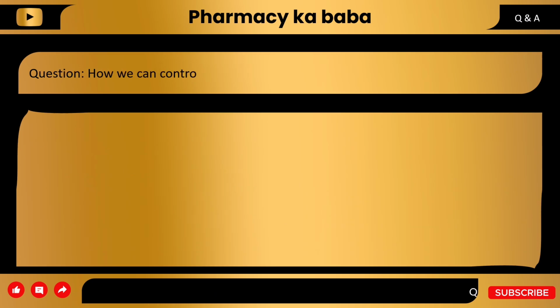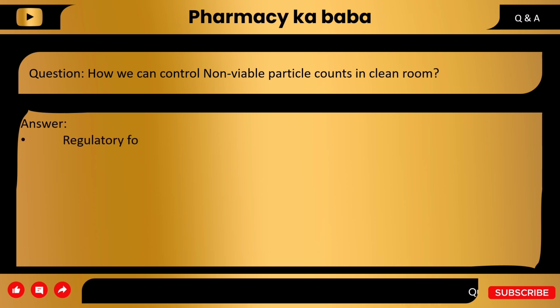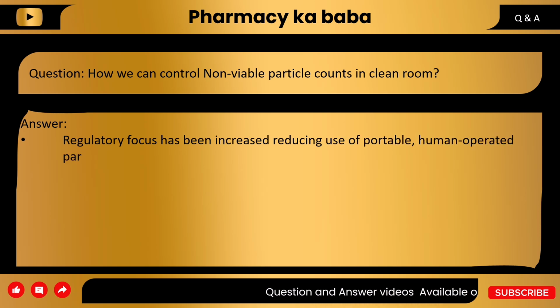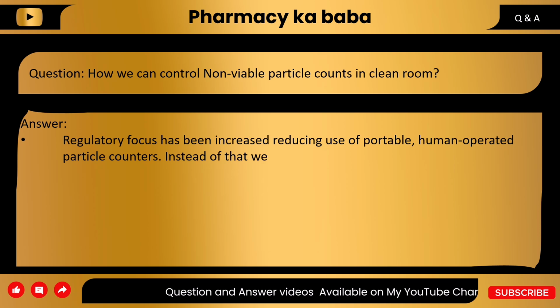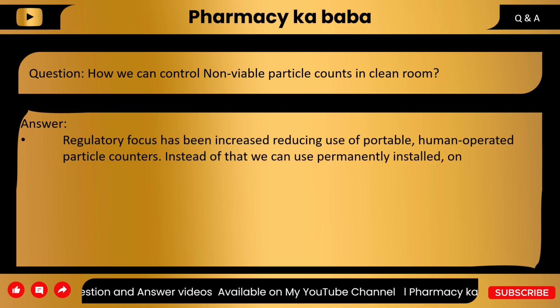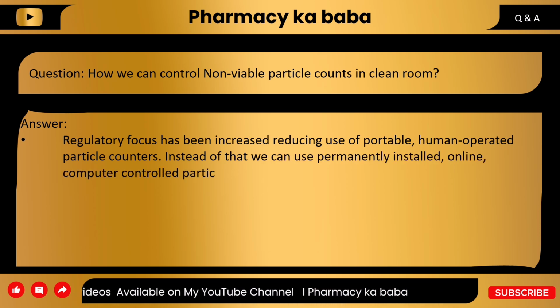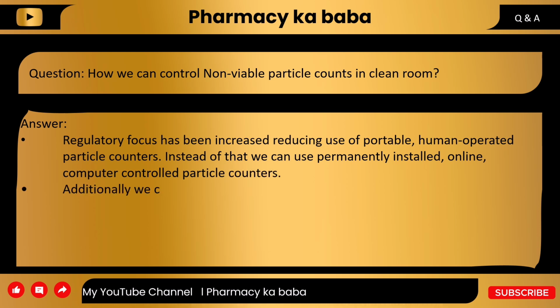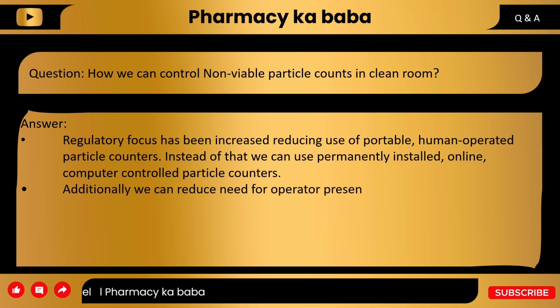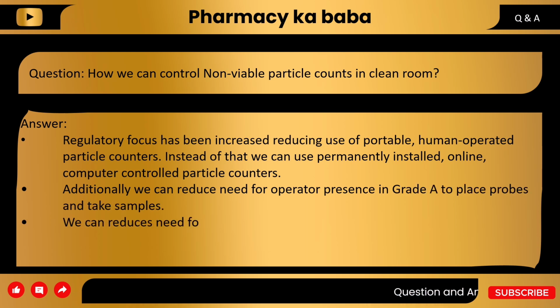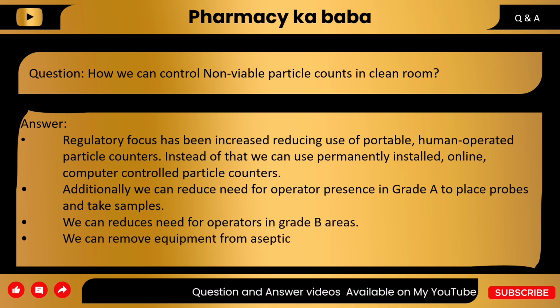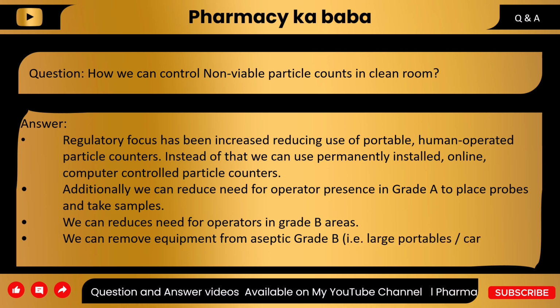Question: How can we control non-viable particles in a clean room? Answer: Regulatory focus has increased on the use of portable human-operated particle counters. Instead, we can use permanently installed online computer-controlled particle counters. Additionally, we can reduce the need for operators to be present in grade A to place the probe and take samples. We can reduce operators in grade B. We can remove equipment from the aseptic grade, that is, large portable counters.